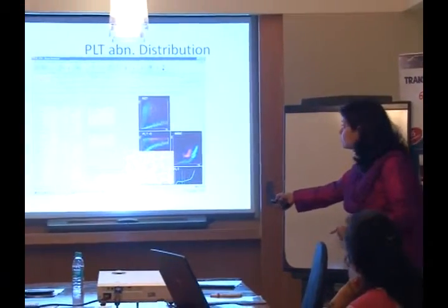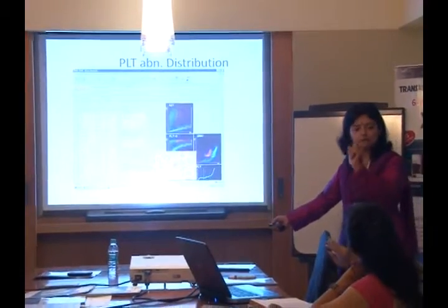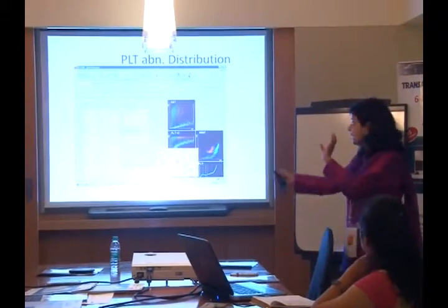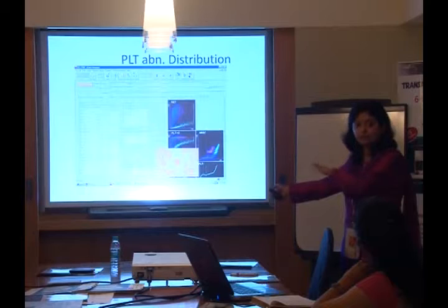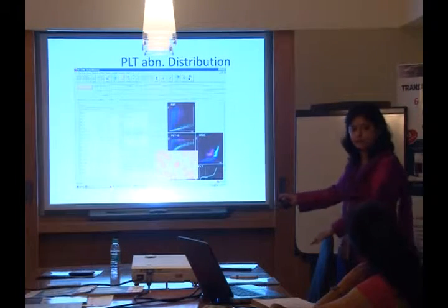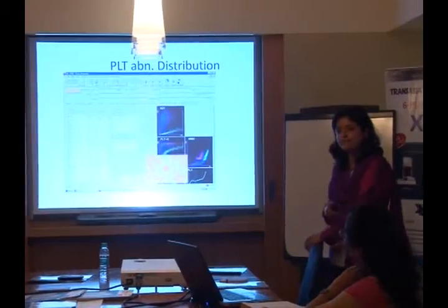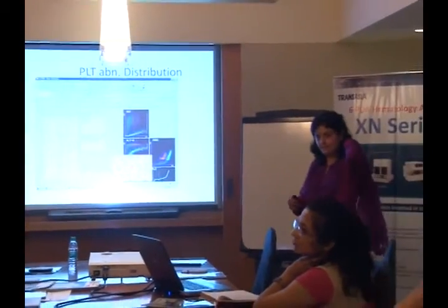Now this screen is not interfaced. It takes the higher optical value. The optical one is more relevant. In this XE, when I come to XN, I will show you I have platelet F now, which I use, which is much more specific. It is far better. The impedance was not counting the large platelets. Impedance doesn't count because the discriminator was fixed up to 20 micron. Even the aggregated platelets may not be counted as one, that is a problem.